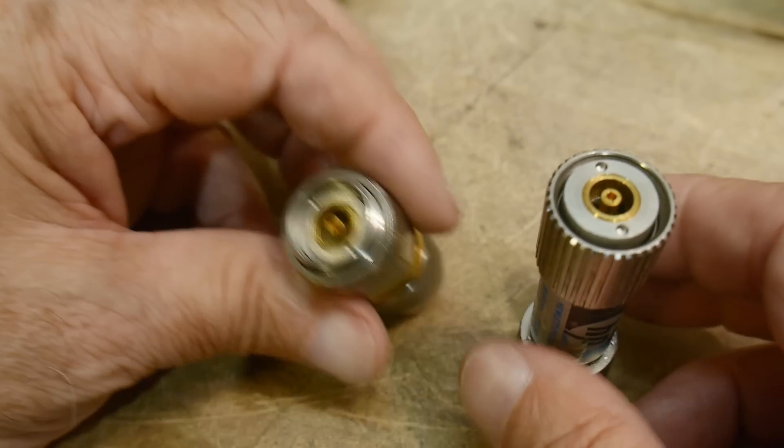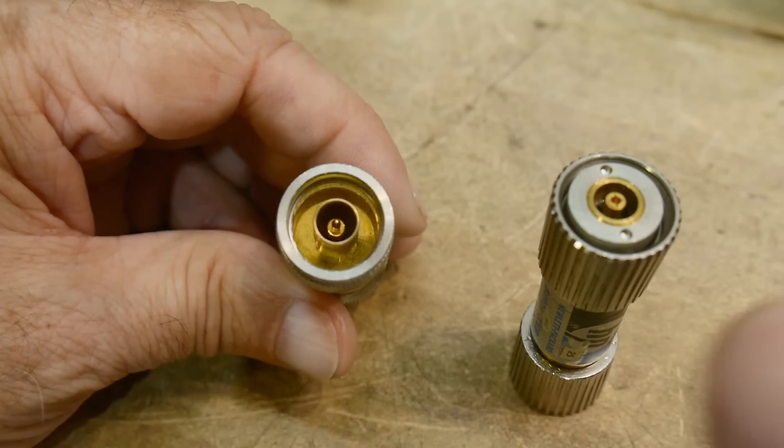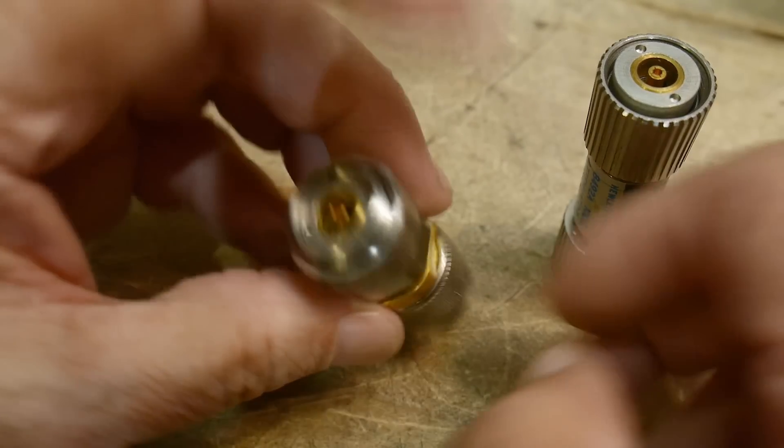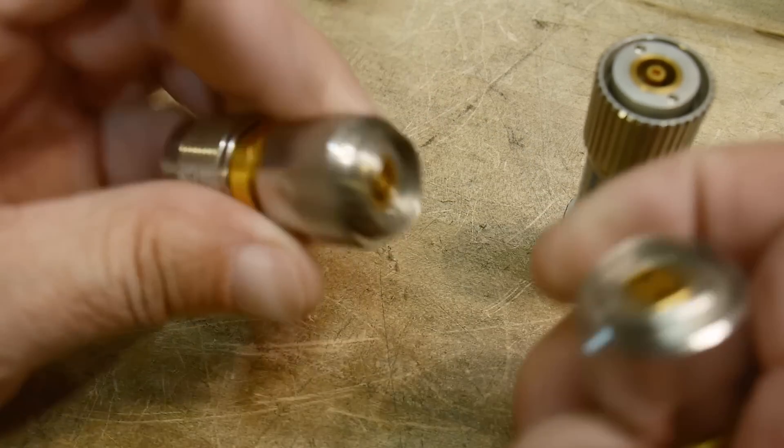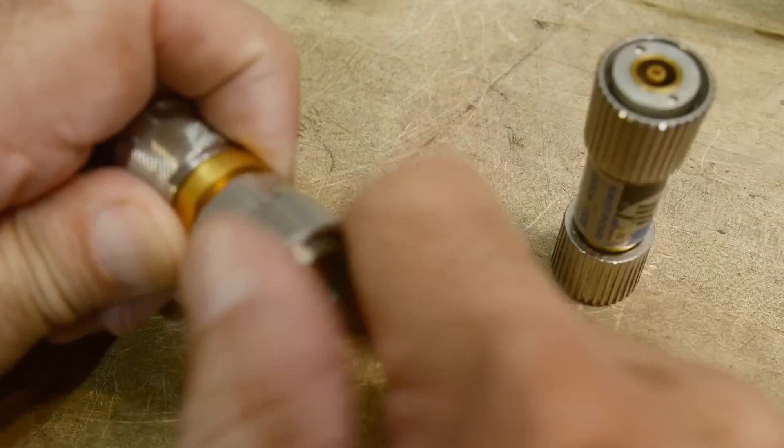Okay, so this is an adapter. This goes from N to SMA, seven millimeter. I have another one here. We can put these together, and we test them. Now these things are good to 18 gigahertz. So they are specified to 18 gigahertz.